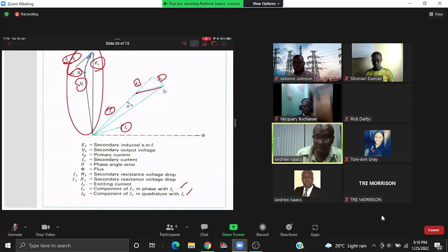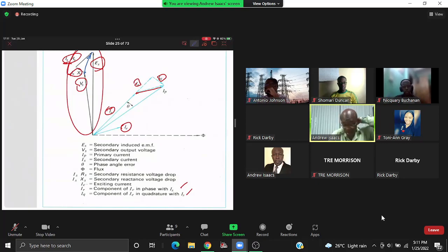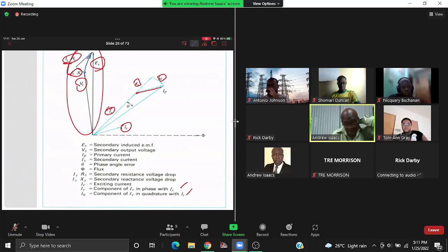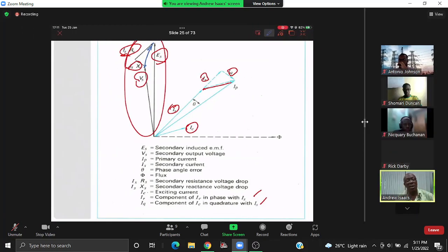Back again. All right. So any questions with respect to the phasor diagram? Because we're just going to make some references to the diagram in terms of speaking of the errors. And I want you to, while we go through this section, just keep in the back of your mind the fact that the primary purpose of the CT is to provide us with a scale replica of what's happening on the system. So if we can reduce the distortion between what's on the system and what we see coming to the relay, then we can make more accurate decisions. All right? So keep that in the back of your head.